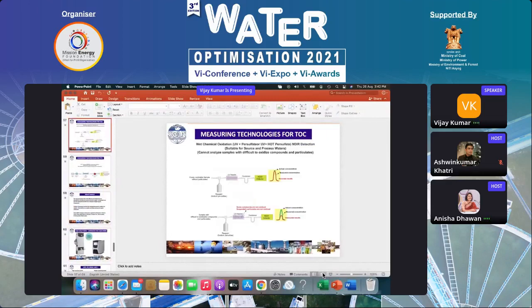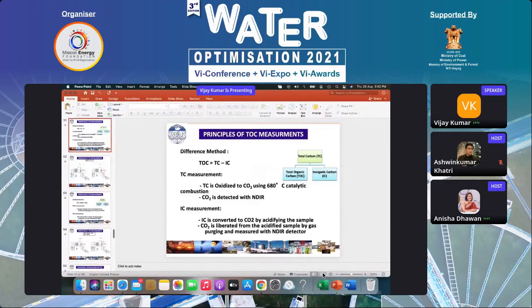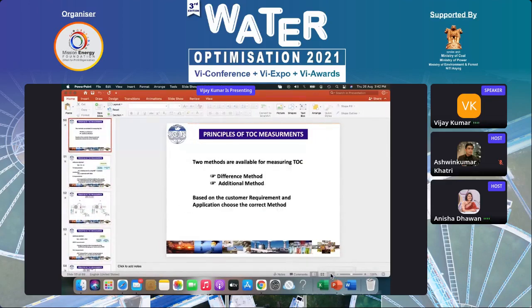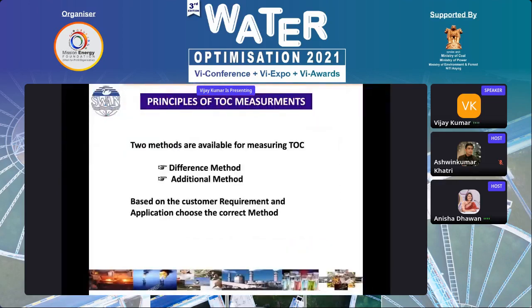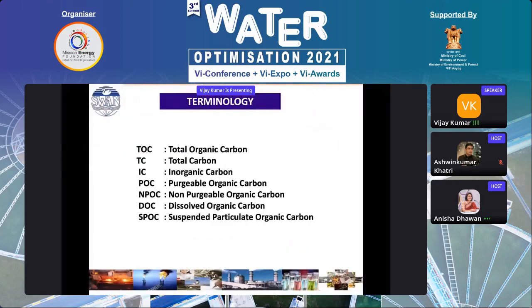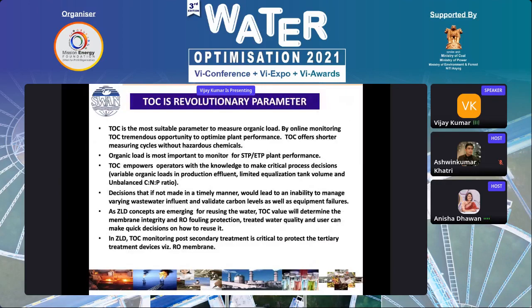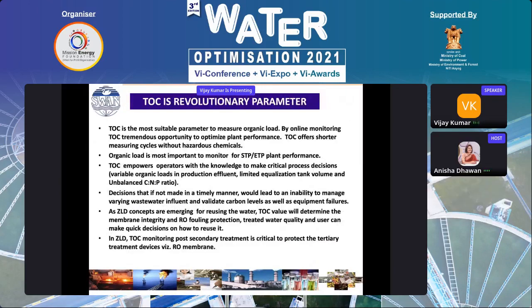So I am trying to explain how TOC analysis is happening. I don't know when it stopped, but let me do it from here. TOC is a revolutionary parameter, the most suitable parameter to measure organic load. By online monitoring, there is tremendous opportunity to optimize plant performance, with shorter measuring cycles. Organic load is the most important for STP and ETP performance, and it empowers the operator with the knowledge to make critical process decisions.